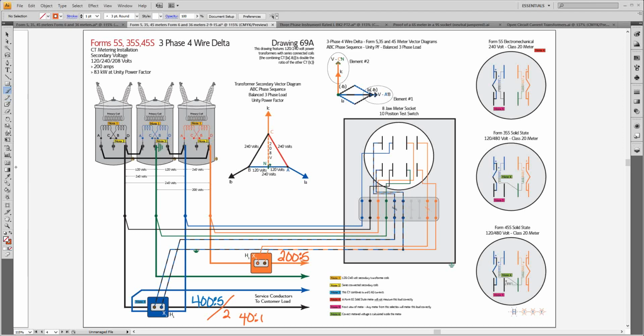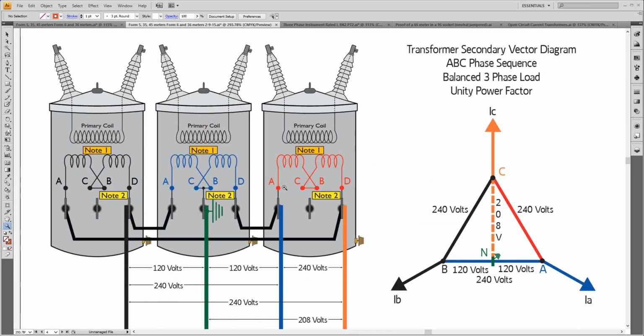And then the dots that connect them in the corners here, I'll zoom in a little bit so you can see, these dots that sit in the corners here are the jumpers that make up the transformer bank. Where blue and red come together, that's this dot right here. Where red and black come together, this jumper that makes up the delta bank is that dot right there. Where black and blue come together, that would be this jumper here. If you have these books, that's how the books are set up as far as the vectoring of the transformer coils, and the vectoring of the transformer coils will relate to what goes on in the meter itself.